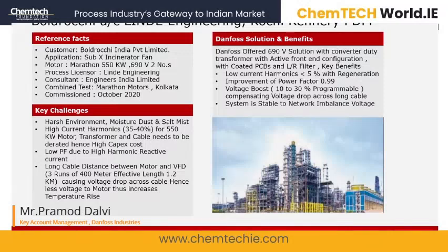And then the third major issue, which in refineries you will see, is that the distance between motor and VFD is high compared to other industries because the motor is sometimes situated in a hazardous area. So in this case, there was a distance of around 400 meters, and since this is a high rating motor, there were 3 runs of cable. So the effective length was around 1.2 kilometers. And what happens due to long distance is there is a voltage drop across the cable, and when the motor sees less voltage, the current goes up and there is a temperature rise in the motor, which is totally unacceptable in this segment.